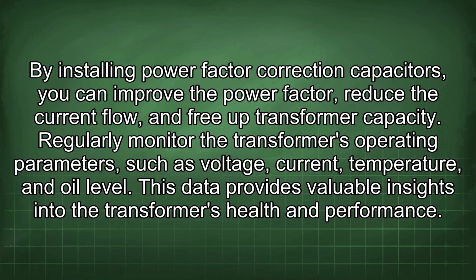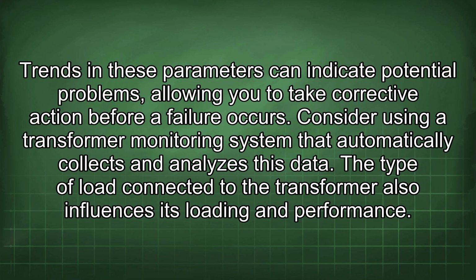Regularly monitor the transformer's operating parameters such as voltage, current, temperature, and oil level. This data provides valuable insights into the transformer's health and performance. Trends in these parameters can indicate potential problems, allowing you to take corrective action before a failure occurs. Consider using a transformer monitoring system that automatically collects and analyzes this data.